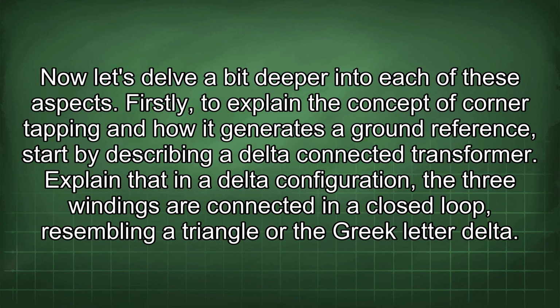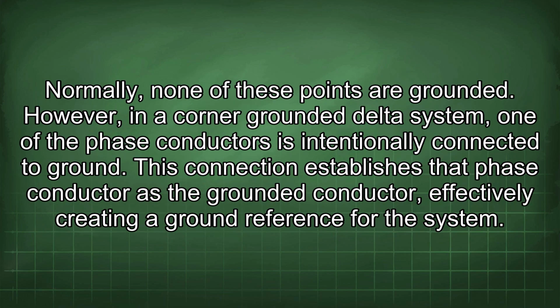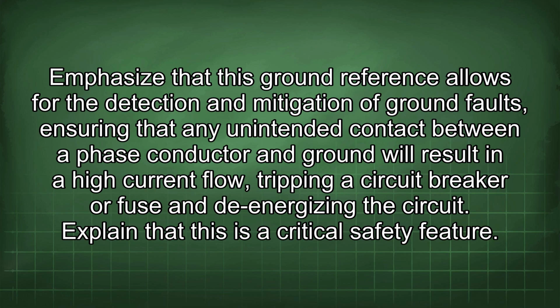Now let's delve a bit deeper into each of these aspects. Firstly, to explain the concept of corner tapping and how it generates a ground reference, start by describing a delta-connected transformer. Explain that in a delta configuration, the three windings are connected in a closed loop, resembling a triangle or the Greek letter delta. Normally, none of these points are grounded. However, in a corner-grounded delta system, one of the phase conductors is intentionally connected to ground. This connection establishes that phase conductor as the grounded conductor, effectively creating a ground reference for the system. Emphasize that this ground reference allows for the detection and mitigation of ground faults, ensuring that any unintended contact between a phase conductor and ground will result in a high current flow, tripping a circuit breaker or fuse and de-energizing the circuit. Explain that this is a critical safety feature.